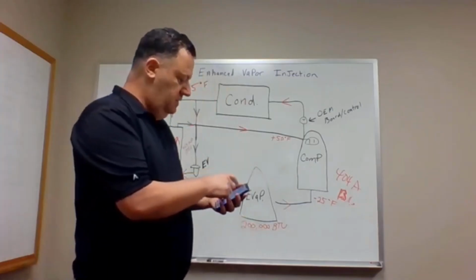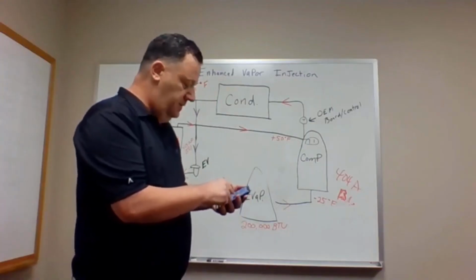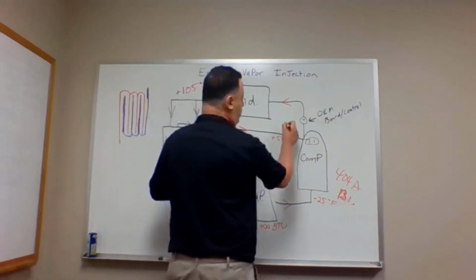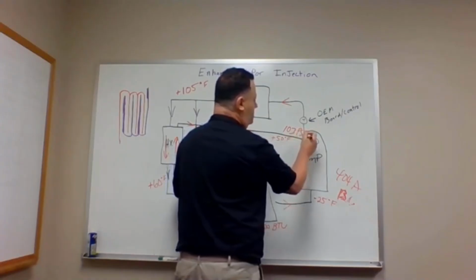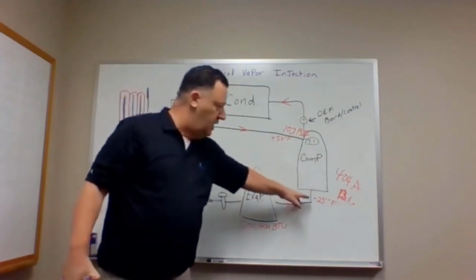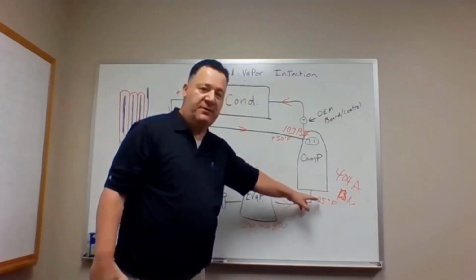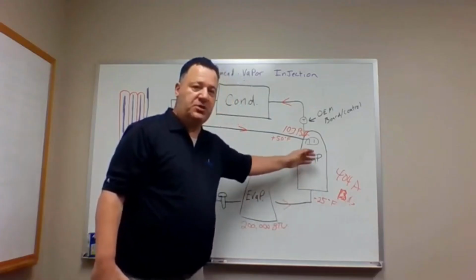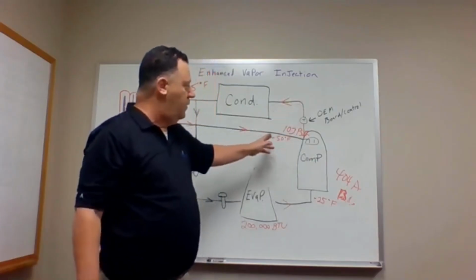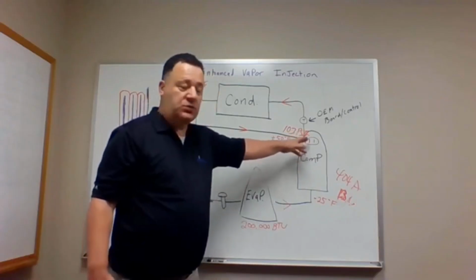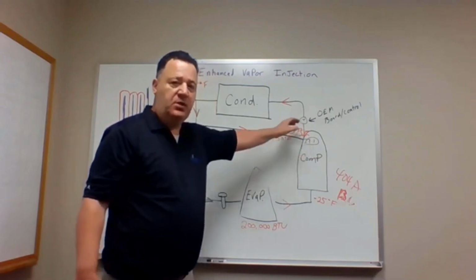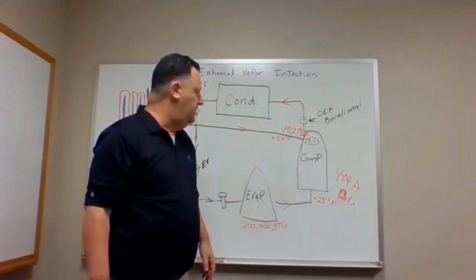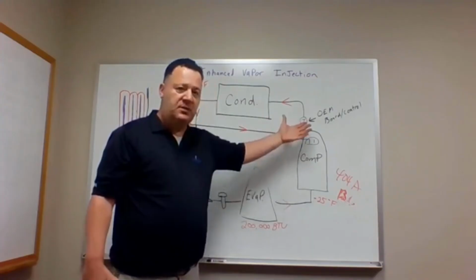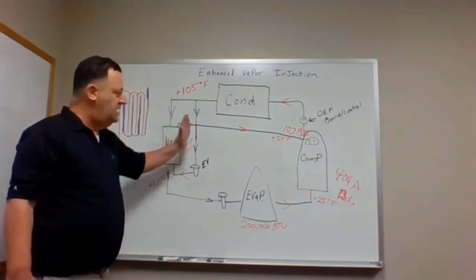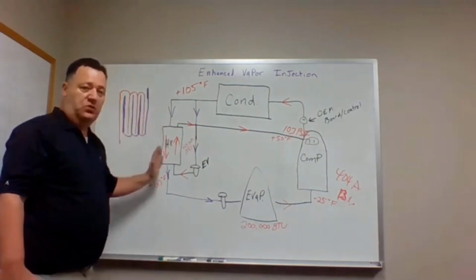Now, if I had plus 50, I would have 103 PSIG, okay, or 104. So instead of going into the compressor at a very low temperature at 13 PSIG at minus 25 and having to do all that work to raise that pressure, to raise that temperature, to hit that discharge line, I'm already injecting this in the intermediate area of the scroll set at 103 PSIG, right in the medium set of the scroll set, okay? So I've already taken a lot of work off that compressor by just using this heat exchanger, by raising the temperature of the vapor, by picking up this subcooled liquid, okay?